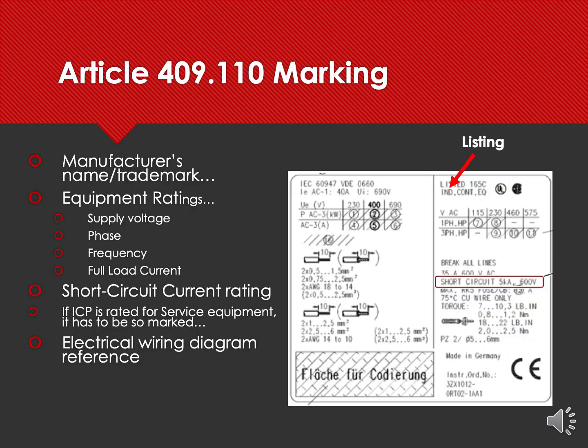Article 409 has some marking requirements that are noteworthy. Of course, it needs to have the manufacturer's name and trademark on it. This is very important because OSHA generally defers to the manufacturer on everything from required maintenance procedures to lockout tagout on systems. So the manufacturer's name is important to have on the gear. The equipment ratings are what you see in yellow, identifying the actual supply voltage. And if there's a transformer associated with it, there'll be a high side voltage and a low side voltage on that transformer. Whether it's single or three phase is important. The frequency of the system, 50 or 60 hertz, or if it's direct current, of course, there is no frequency, and full load current on the equipment as well. Those are just some of the markings that are expected to be on there with respect to equipment ratings.